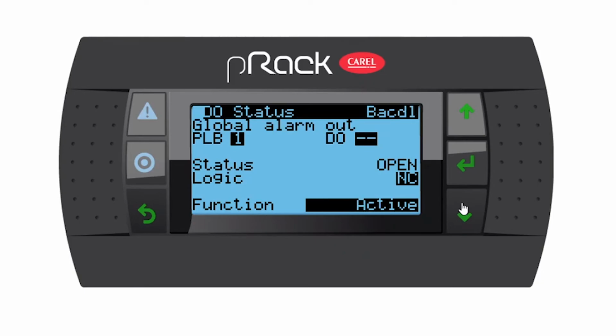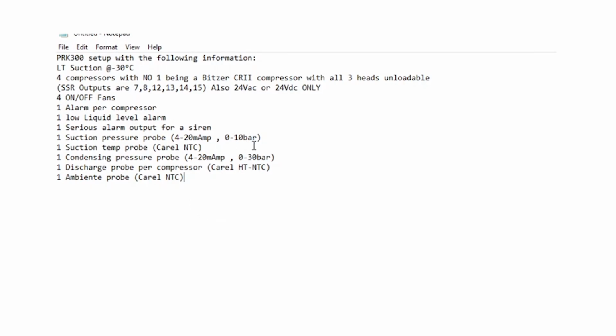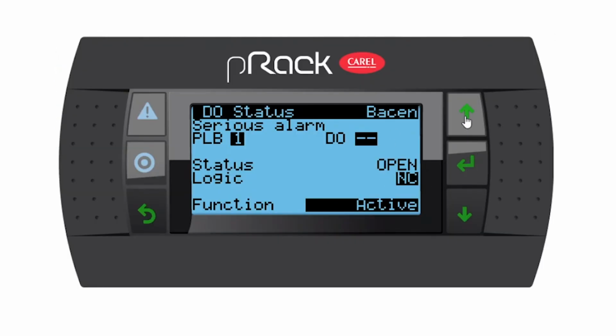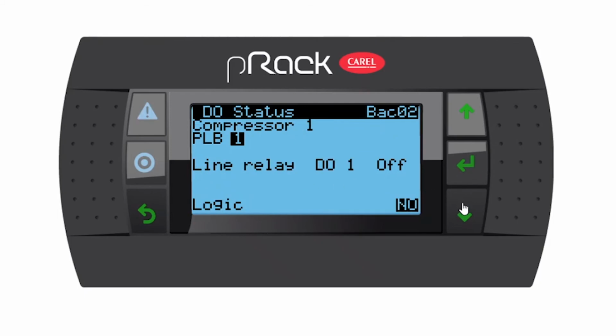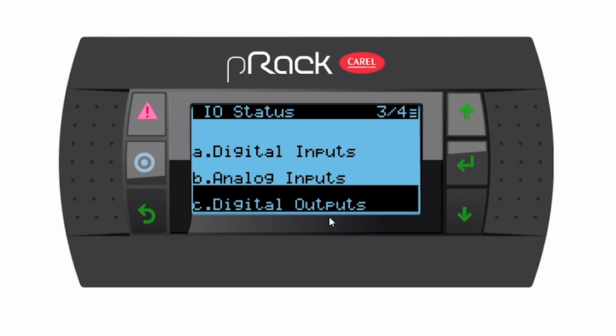Do you have a global alarm output? If you do, assign it. A live signal, a BMS forced output, a normal alarm, and a serious alarm. So remember, in the notes I said we've got one serious alarm output for a siren. So I'm going to assign it, and I'm going to make it on the latter stage of my outputs, so number 18. Perfect. And a normally closed. And then we're back at the beginning. Awesome.